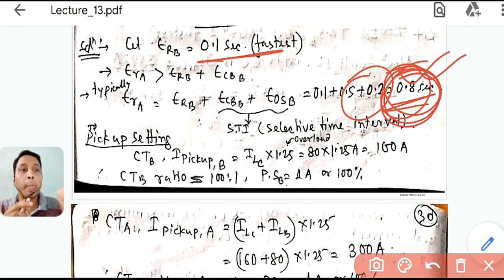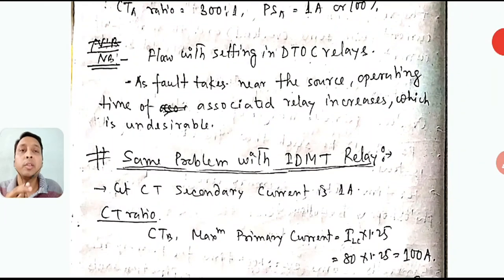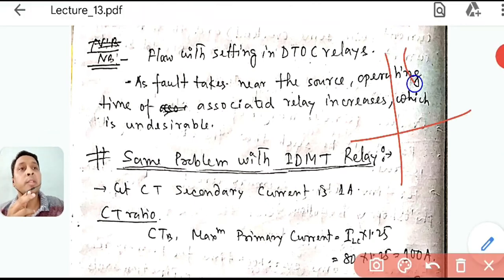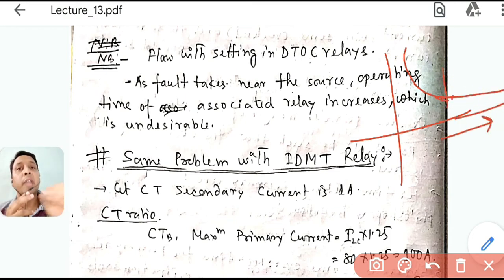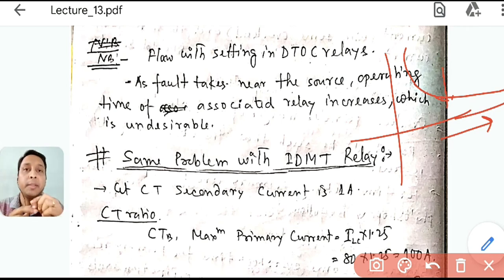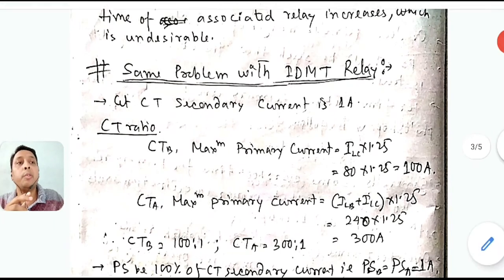The solution is to use an IDMT (Inverse Definite Minimum Time) relay. The IDMT relay exploits inverse characteristics: as fault current increases, operating time decreases. So for severe faults, the relay operates faster. We will now solve the same coordination problem using IDMT relays.